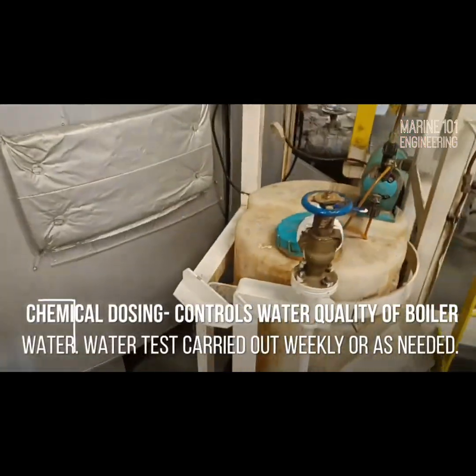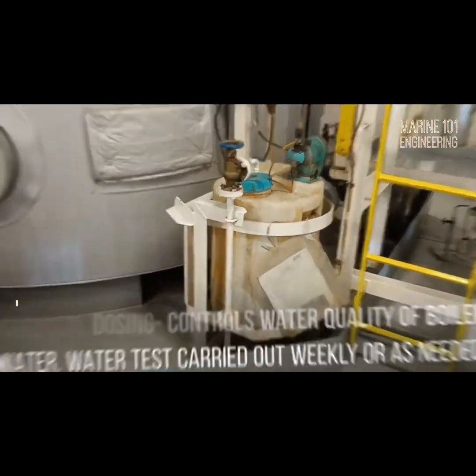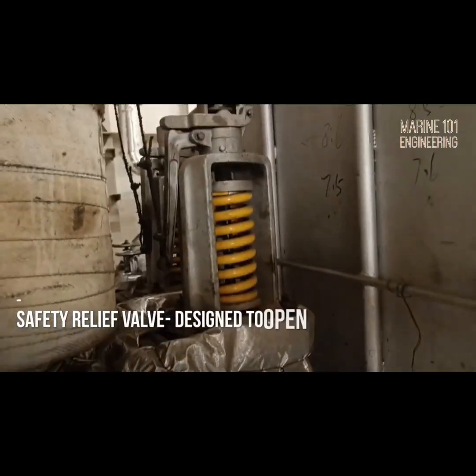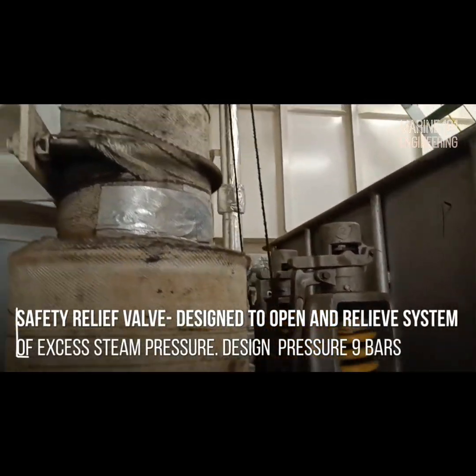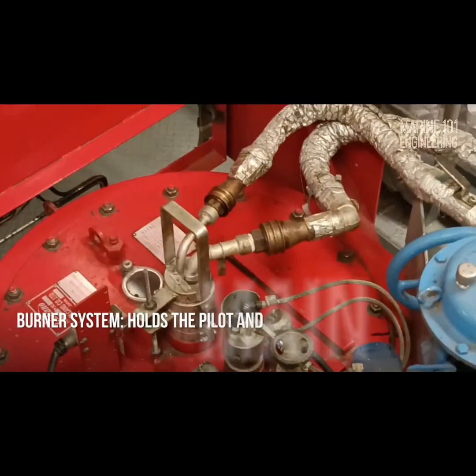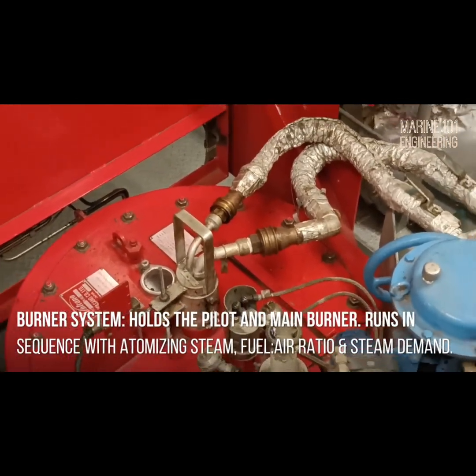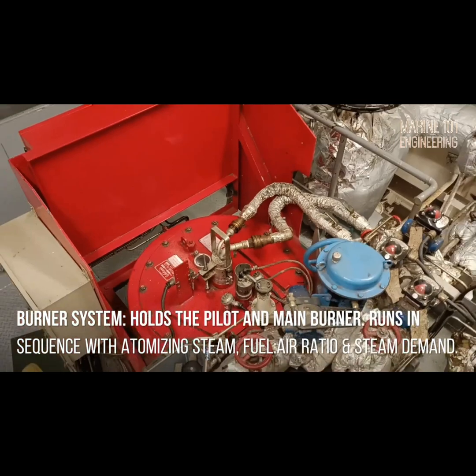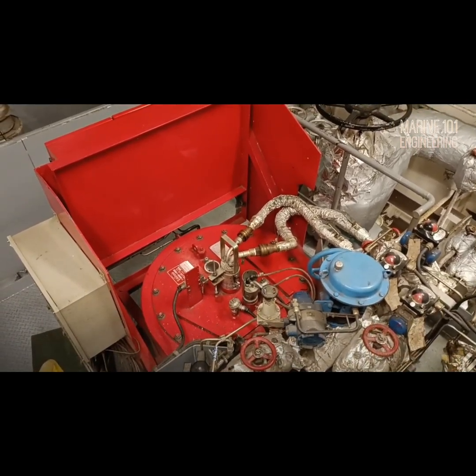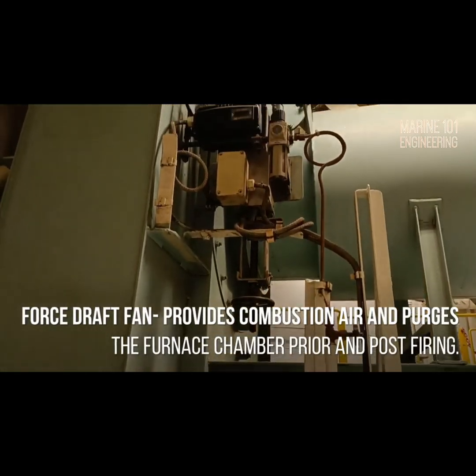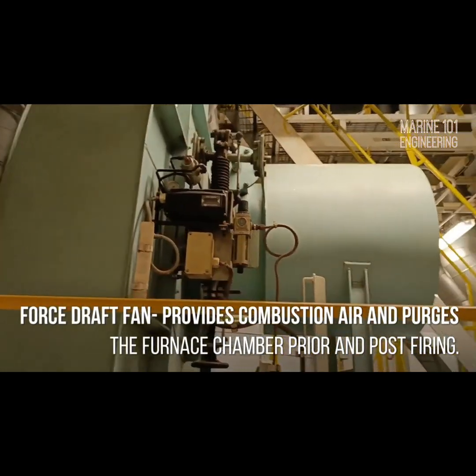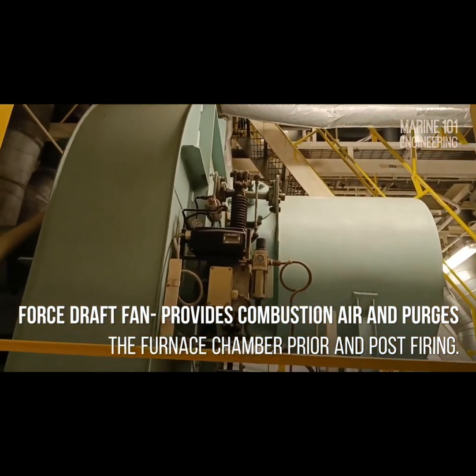Chemical dosing pump delivers chemical treatment into the feed water line. Quantity of dosage shall be based on water test results. Safety relief valves open to release excess steam in the system at factory adjusted setpoint. On this boiler design, 9 bars opening pressure. Forced draft fan provides air flow for boiler operations such as during purging and combustion.